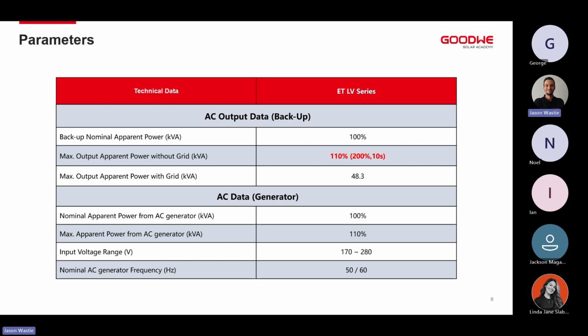Next is the AC output data. So this is on the backup side. So on the backup side, we can constantly output up to 110%, meaning on the 15 kilowatt unit, we can do up to 16.5 kilowatts. And then at the same time, we can run up to 200% overloading for up to 10 seconds, which means we can handle up to 30 kilowatts of load for 10 seconds on the 15 kilowatt unit, 40 kilowatts on the 20 kilowatt unit. And how we do that is through the DC capacitor bus built into the inverter itself. So we don't do this through the batteries. We don't obviously do it directly through the PV.